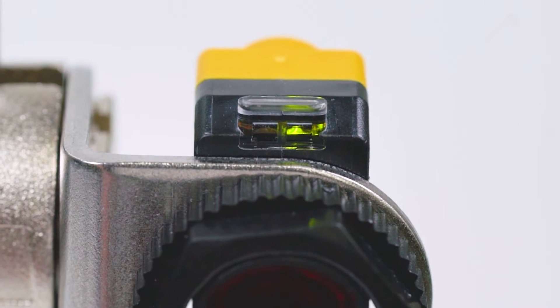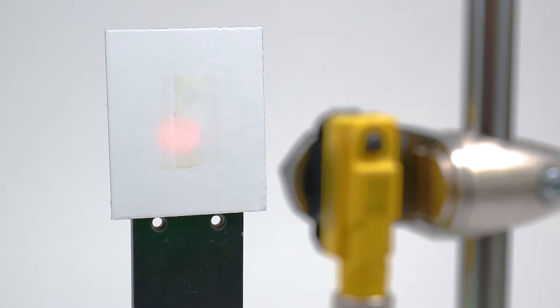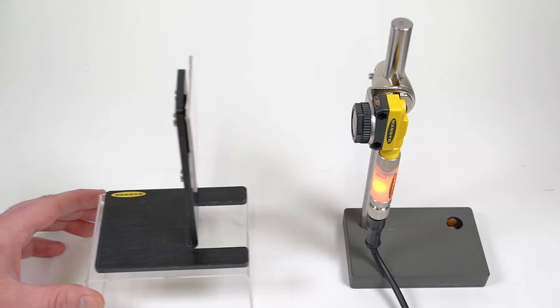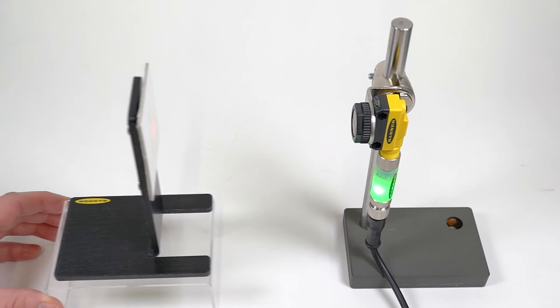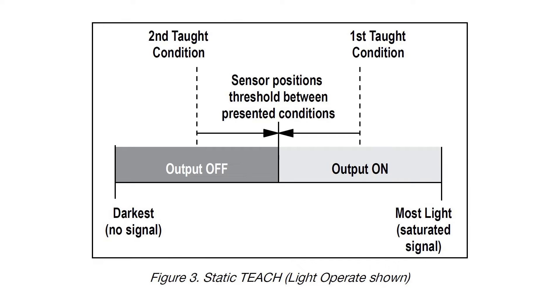Welcome to a short how-to video that will cover the static teach mode for the QS18 Expert photoelectric sensors from Banner Engineering. The static teach mode measures the light returning to the receiver in two separate conditions and sets the switching threshold between them.